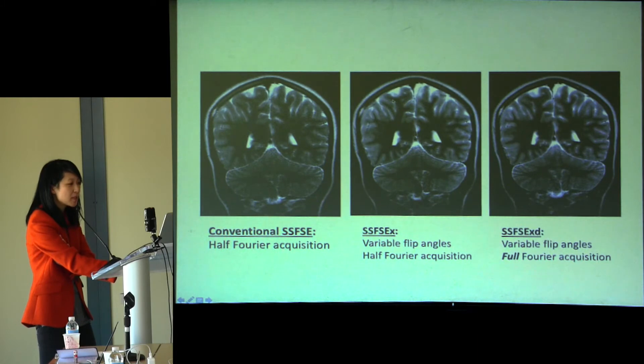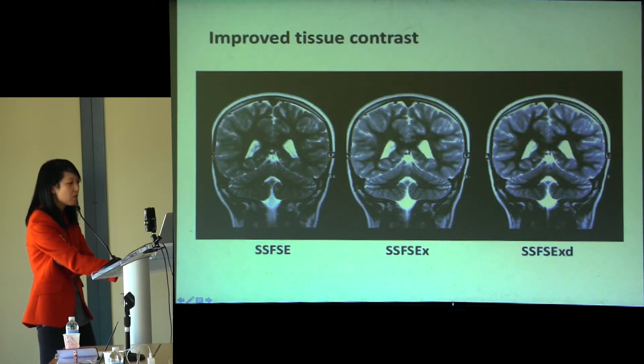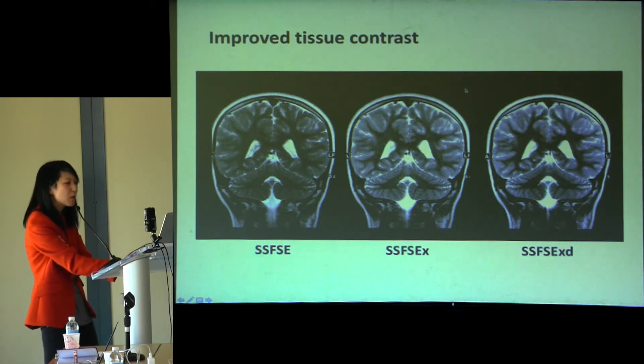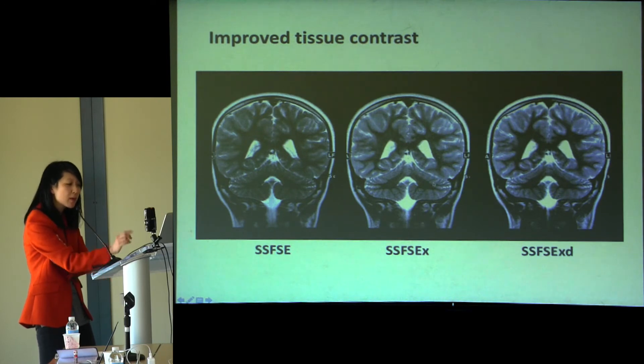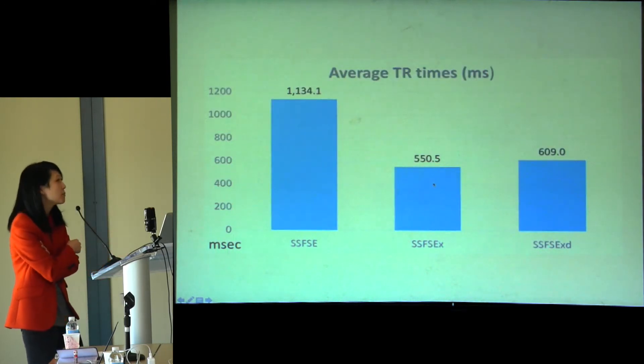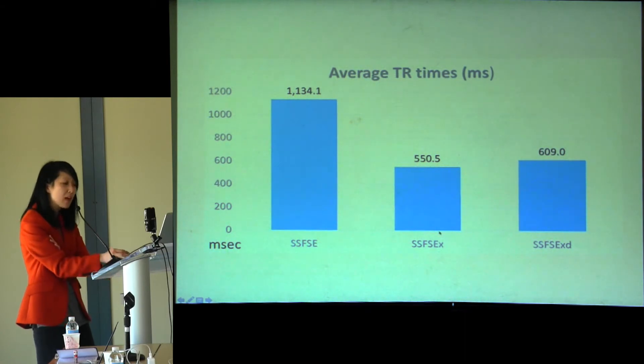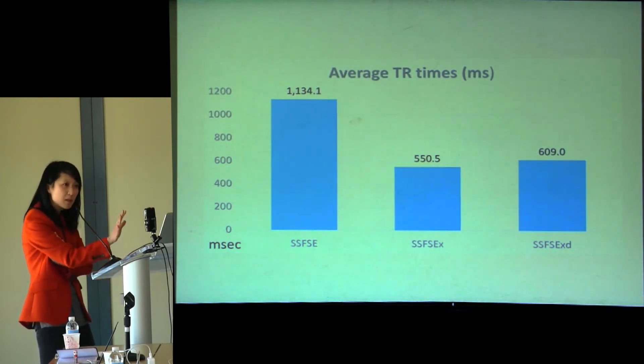One thing we're exploring is using variable refocusing flip angles for improved image quality and faster scan time. Here's some preliminary data: with conventional fast MR, images look flat. After applying variable flip angles, you start seeing gray-white differentiation better. Another example — with a change in refocusing flip angle, it starts to look like a real T2 image, the kind we use day-to-day at three to five minutes depending on magnet strength. These are much faster — half the time of even the current fast scan — at around 1100 milliseconds, and less sensitive to motion.